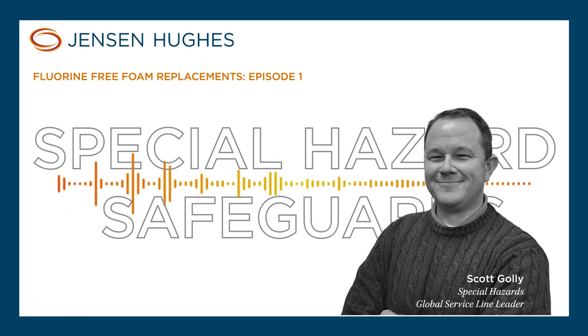That fuel vapor seal is what we've lost in fluorine-free foam. The film reseals quickly — I have fond memories from Fire Academy of putting out fuel fires and then intentionally shaking the foam with sticks to relight the fire, and the foam would push back in and put it right back out. The foam blanket limits oxygen access to the fuel and vapor transport to the fire, and it adds and maintains a cooling effect and blanketing effect over time.